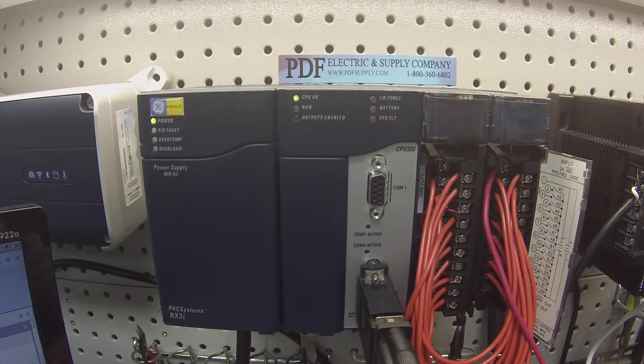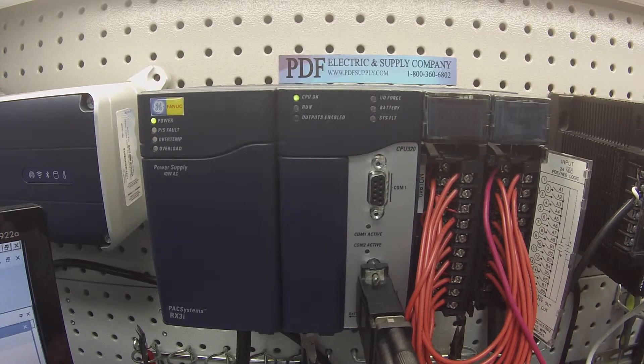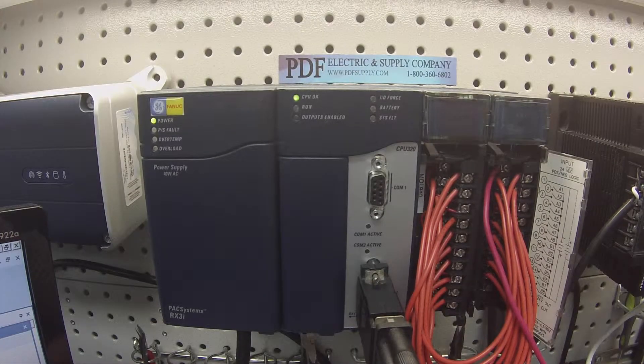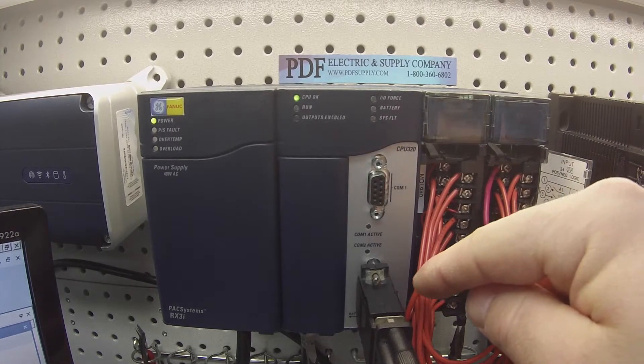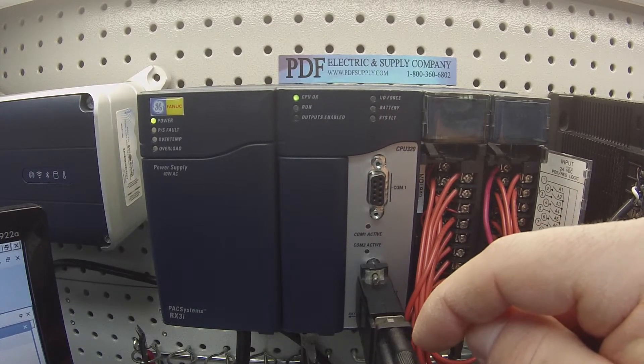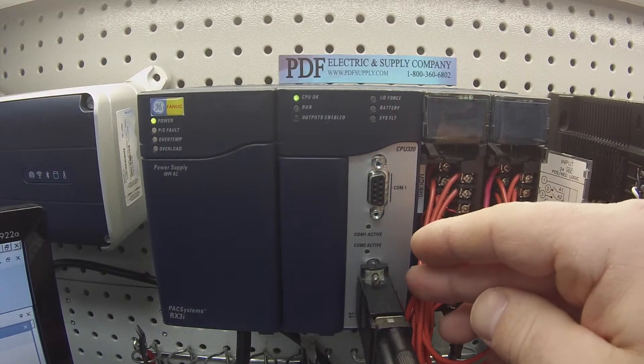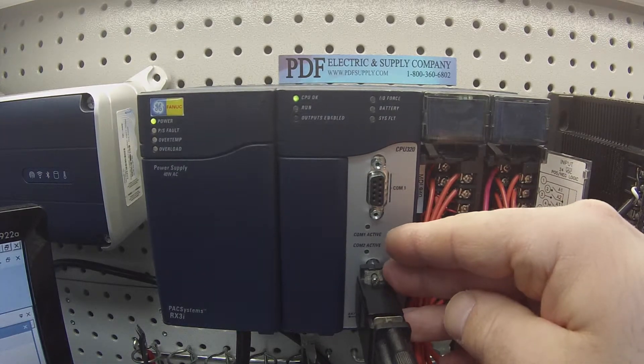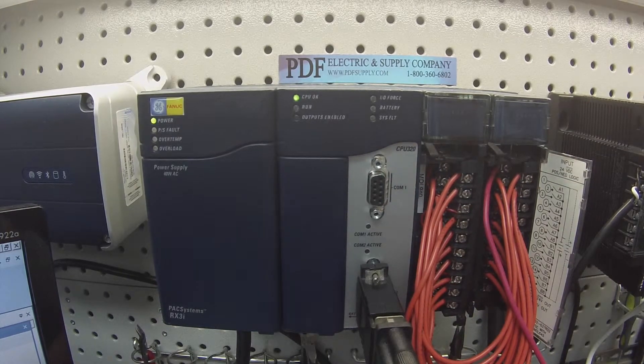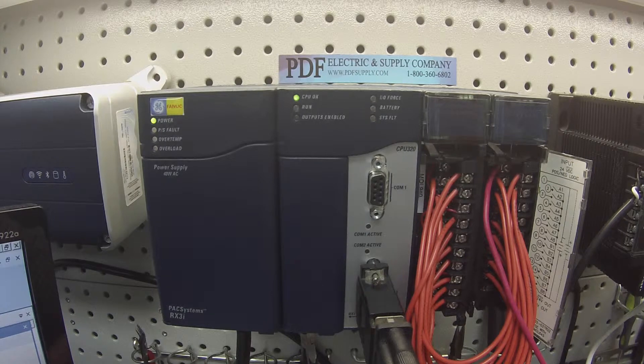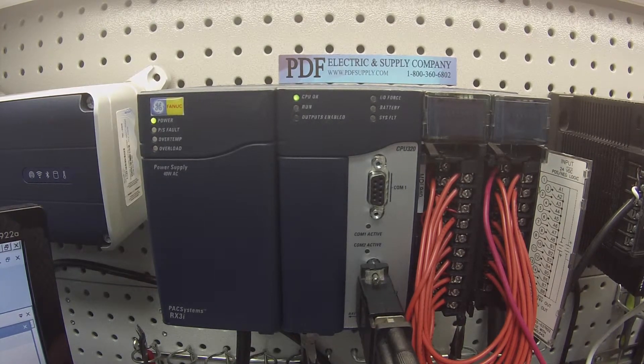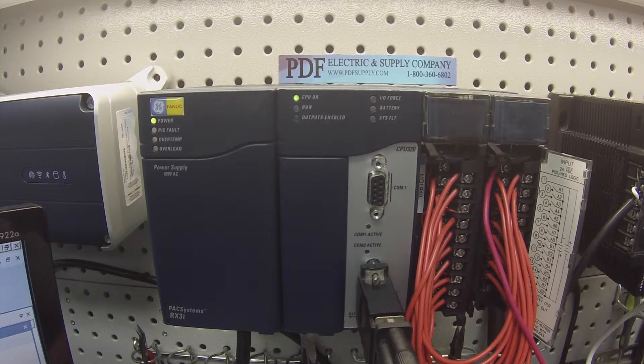So the next step is going to be in the software. I'm using Proficy Machine Edition and I'm going to connect up to the processor using a HE693SNP CBL cable and I'm going to use an HE693SNP232 connector in order to get to this COM port number 2. Let me back up, that's an HE693CBL232 cable attached to an HE693SNP232 connector. The reason I'm using a connector is because my COM port number 2 is a 15 pin so I need to convert from 9 to 15 pin.